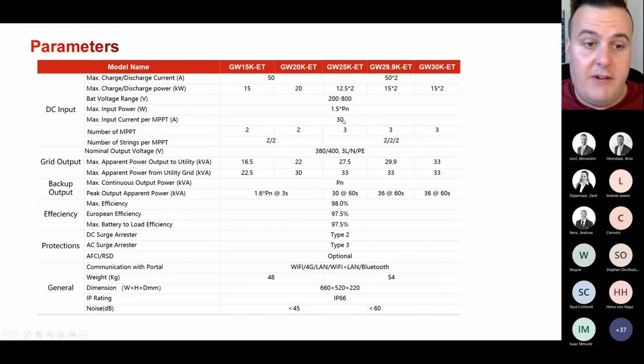Then our MPPT rating on these inverters is 30 amps per MPPT. So that gives us a wide range. As you'll see, the 15 and 20 have 2 MPPTs, the 25 and 30 have 3 MPPTs, and it's 2 inputs per MPPT. So that's 15 amps per input or a combined 30 amps.